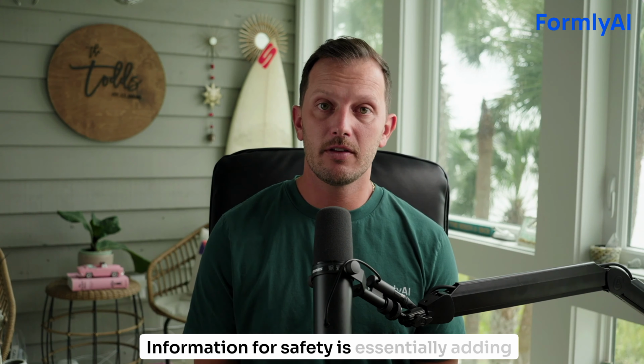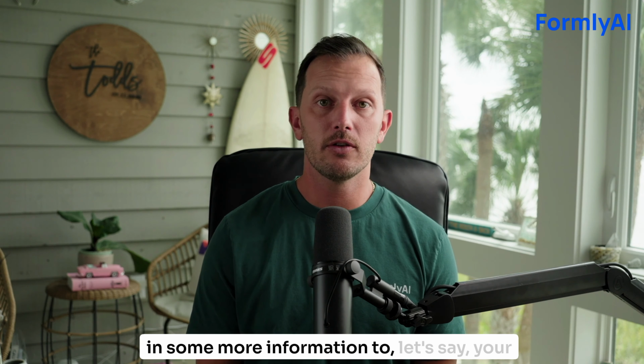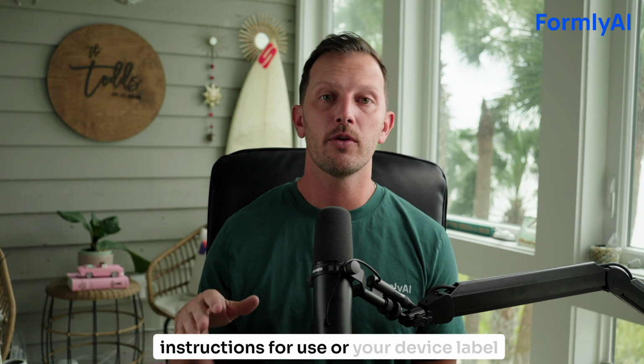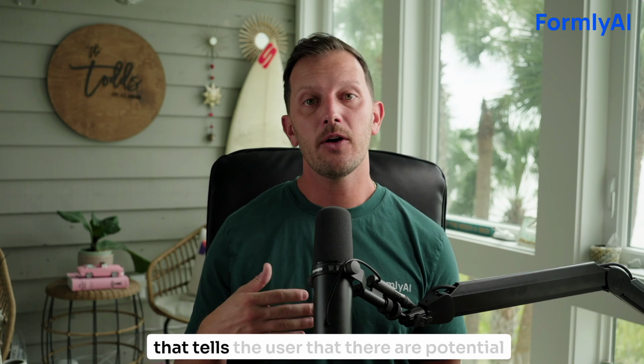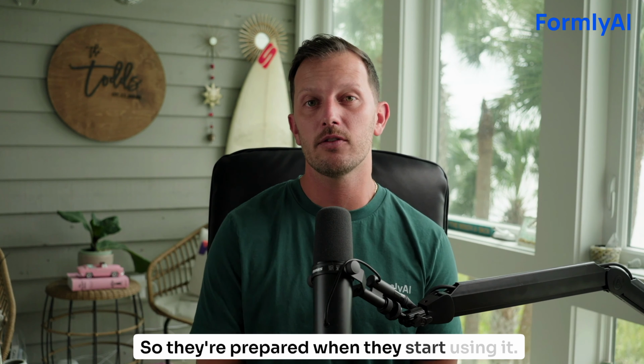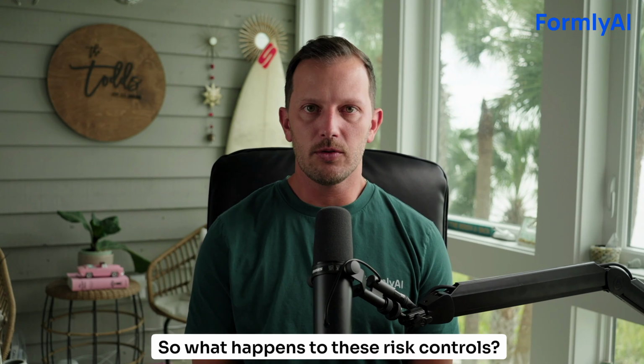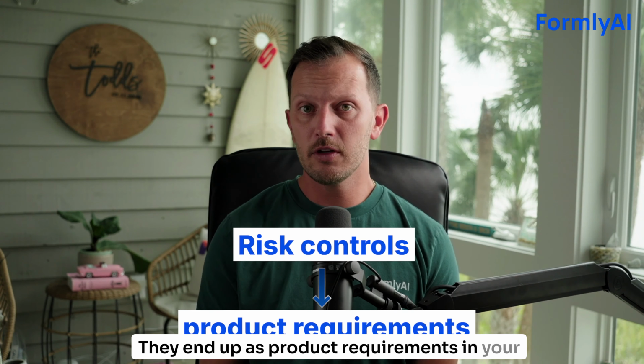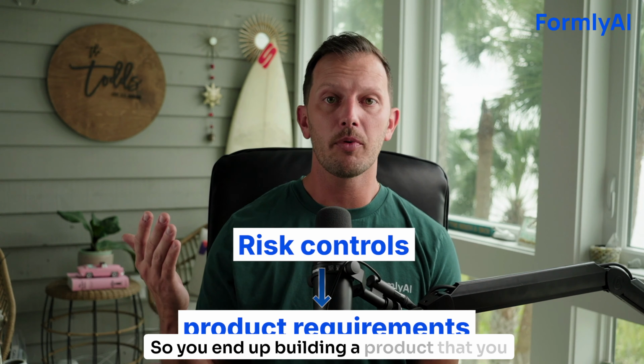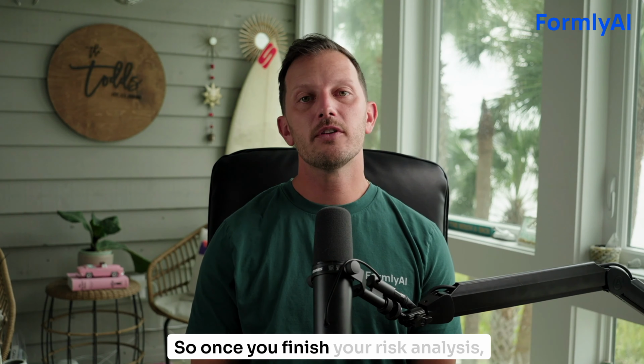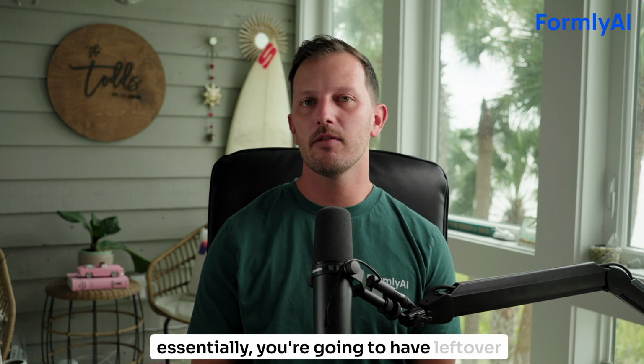Information for safety is essentially adding in some more information to, let's say, your instructions for use or your device label that tells the user that there are potential risks with using the device, so they're prepared when they start using it. So what happens to these risk controls? They end up as product requirements in your medical device, so you end up building a product that you know is safe.